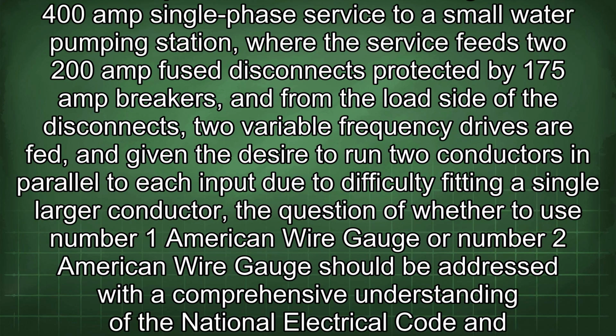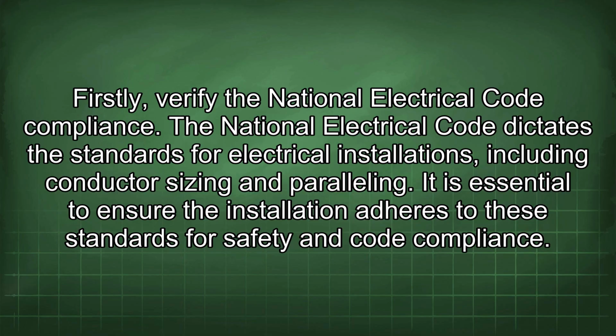For the specific scenario of installing a new 400 amp single-phase service to a small water pumping station, where the service feeds two 200 amp fused disconnects protected by 175 amp breakers, and from the load side of the disconnects, 2 variable frequency drives are fed, and given the desire to run 2 conductors in parallel to each input due to difficulty fitting a single larger conductor, the question of whether to use number 1 American wire gauge or number 2 American wire gauge should be addressed with a comprehensive understanding of the National Electrical Code and the principles of electrical engineering. Firstly, verify the National Electrical Code compliance.